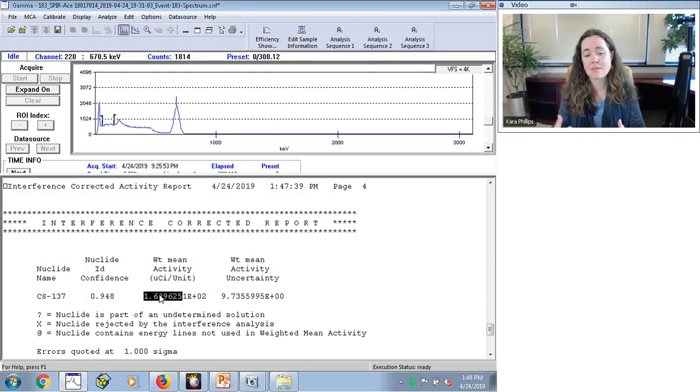And so I can take the same concepts that I did here, and I can actually save a new calibration file and load that right back into the SPIR-Ace device, so I can have that as a selection on board if I need that as well. So we're not just limited to those predefined ones that you already find on the device.